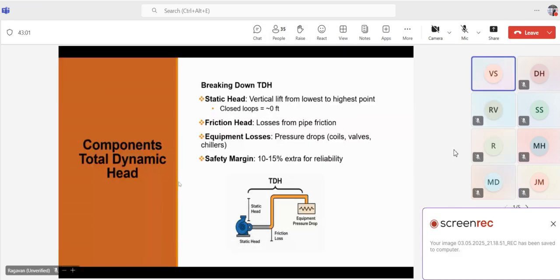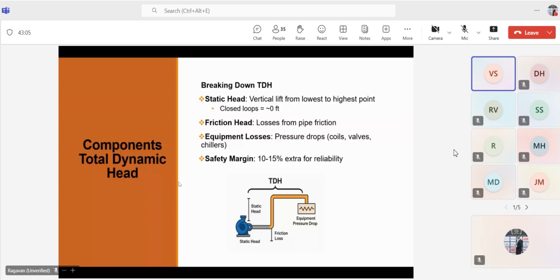And then the friction losses. The friction losses refer to the pressure drop that occurs as water flows through the pipes, fittings, and valves of the chilled water system, due to the resistance caused by the internal surface of the components. These losses of pressure must be overcome by the pump. So it is a critical part of the head calculation.